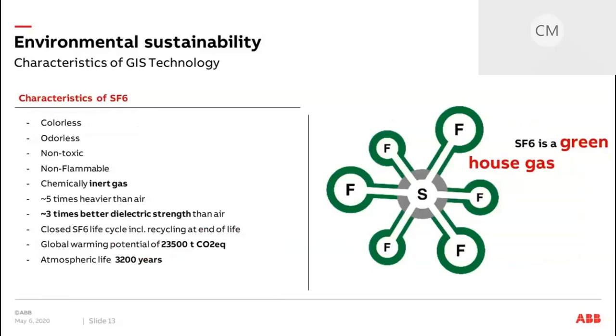Lately, we have also sold one switchgear that combined both the features of digital switchgear and Air+. So when we talk about GIS, we also have to talk about the isolating gas. Usually, you use SF6, so sulfur hexafluoride, which has a couple of unique characteristics. You can't see it, you can't smell it, it's non-toxic, it's non-flammable, and it's a chemically inert gas, so it doesn't react with any of the materials inside the gas compartment.